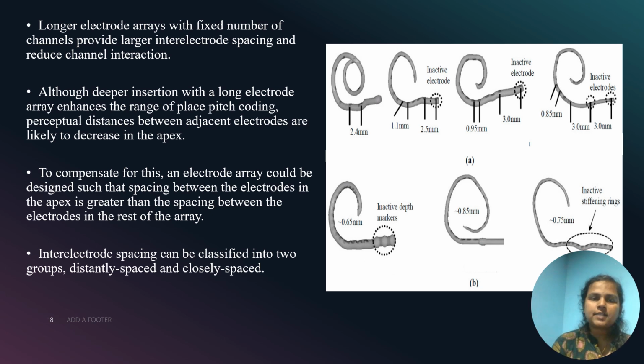Longer electrode arrays with a fixed number of channels provide larger inter-electrode spacing and reduced channel interaction. Although deeper insertion with a long electrode array enhances the range of place pitch coding, perceptual distances between adjacent electrodes are likely to decrease in the apex region. To compensate for this, the electrode array could be designed such that spacing between the electrodes in the apex is greater than the spacing between the electrodes in the rest of the array, that's the basal end.